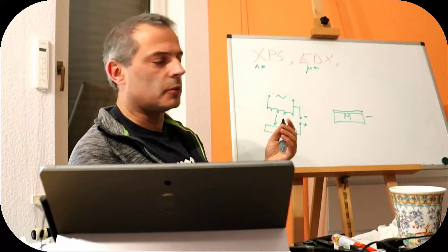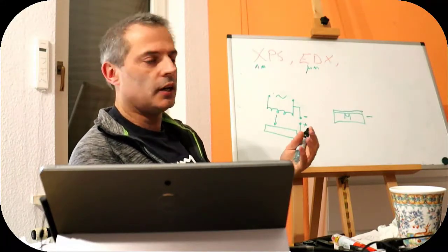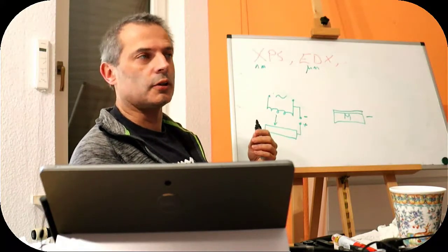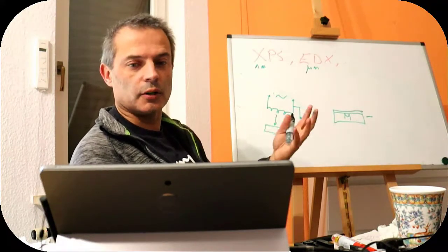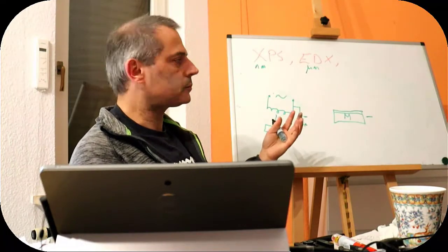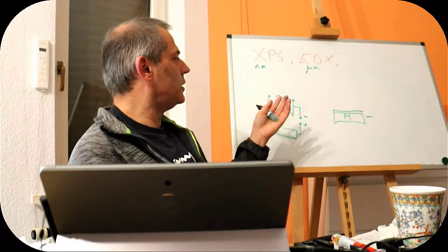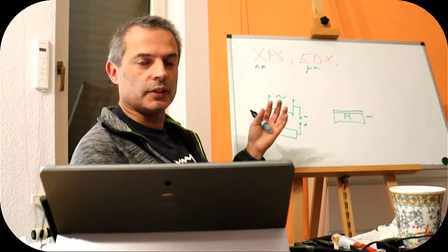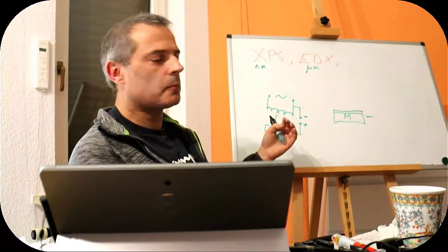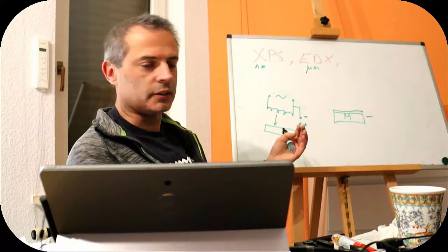Because the electrons have a very high energy and the process isn't super efficient, we also need to cool our electrode if we're going to get high energies out, high flux, a lot of X-rays out, because otherwise it will melt. It can get hot very quickly, partly because we always forget, because we live in the normal world, that in a vacuum it's hard for heat to get out of things.